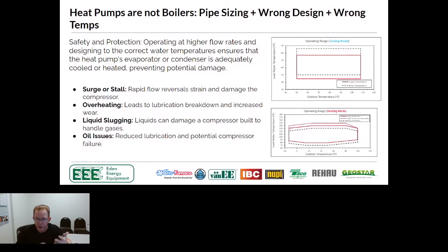We make sure that we understand 2 to 3 gallons per minute on a hydronic heat pump. As soon as you redo the math at 2 to 3 gallons per minute, you're going to find that you're actually going to end up with the right flow rates, because the 2 to 3 is assuming a 5 to 8 degree delta T, not a 20 degree delta T. By having the right flow rate through that piece of equipment, it means we're not going to have issues with anything happening inside of the unit. So what I mean by that is we're not going to have any overheating of the compressor, which obviously causes problems with the oil. Any of you who were in Trevor Matthews' presentation, he had a great presentation where he talks a lot about different things you want to pay attention to on compressor bearing units. We definitely don't want to overheat it. And the reality is if you have water that's constipated, that's what I call it when it's stuck in the heat pump, this dotted line, you are 100% going to hit it.